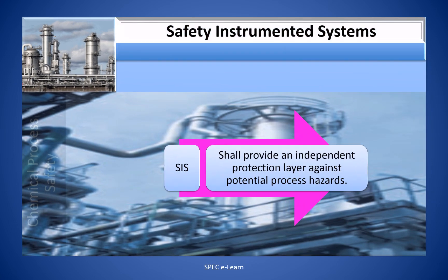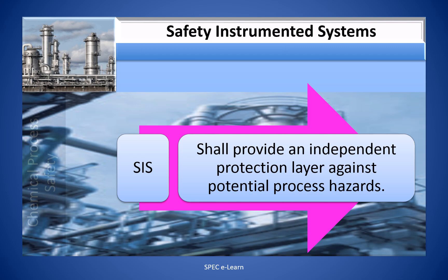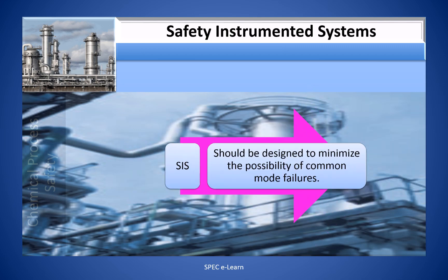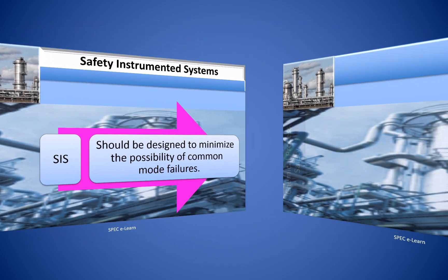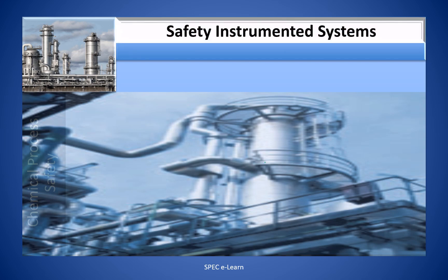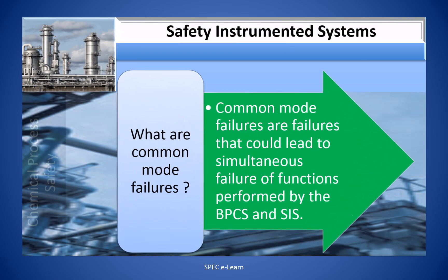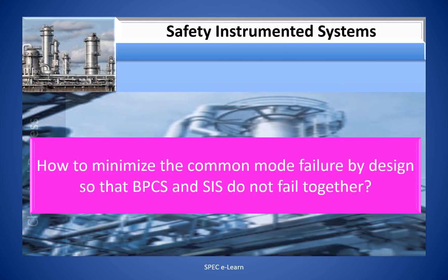The SIS shall provide an independent protection layer against the potential process hazards. SIS should be designed to minimize the possibility of common mode failures. Common mode failures are failures that could lead to simultaneous failure of functions performed by both BPCS and SIS. The design goal is to ensure that BPCS and SIS do not fail together.